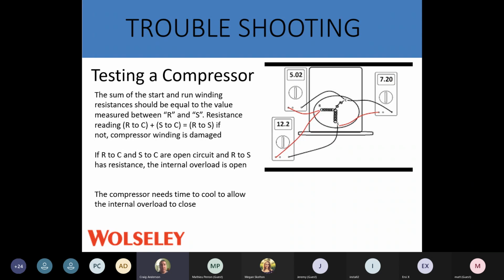What I mean by internal overload: if you get to a job site, everything's working and the compressor's not coming on, turn it off. If you can reach in there and touch your compressor, and you can barely touch it, it's so hot, then chances are the internal overload is open on that unit. So you need to wait till it cools down. You have two options at that point. You can try pouring some water on it to cool the compressor down to see if we can get that overload to go back to normal. Or you're going to look at the customer and say, I'm going to see you later this afternoon, or I'm going to see you tomorrow, because that unit needs to cool down to see if that overload goes back. If the overload doesn't go back, then we have a damaged compressor and it needs to be changed.